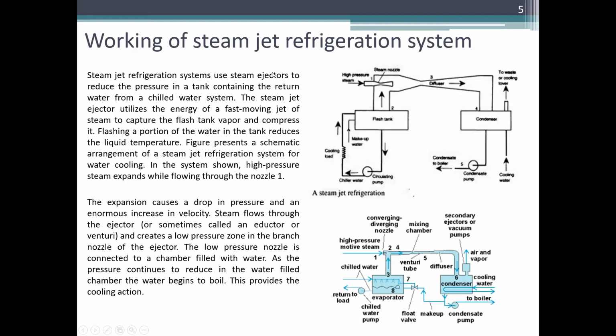So, working of steam jet refrigeration cycle. Same lang yan. Steam jet refrigeration system uses steam ejectors to reduce the pressure in a tank containing the return water from a chilled water system. The steam jet ejector utilizes the energy of a fast-moving jet of steam to capture the flash tank vapor and compress it. Flashing a portion of water in the tank reduces the liquid temperature. The figure represents the schematic arrangement of a steam jet refrigeration system for water cooling. In this system, high pressure steam expands while flowing through nozzle 1.